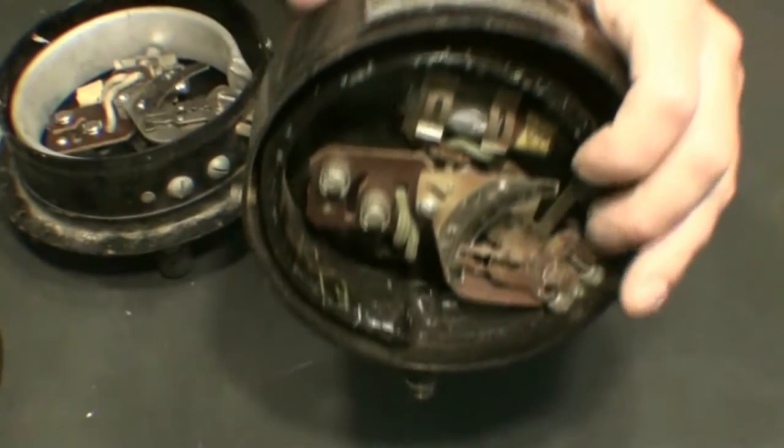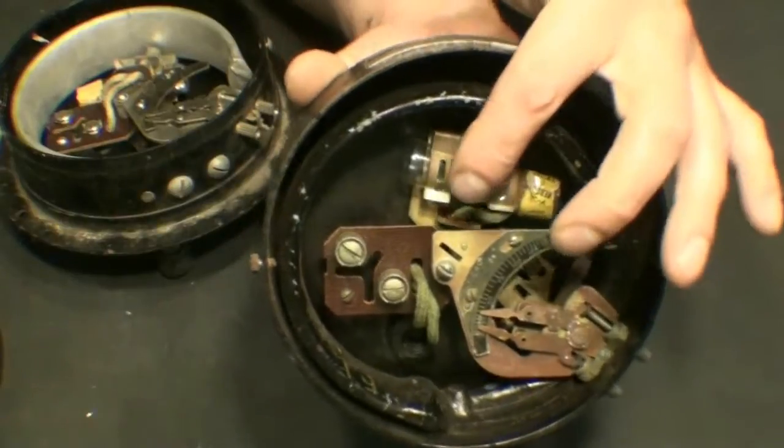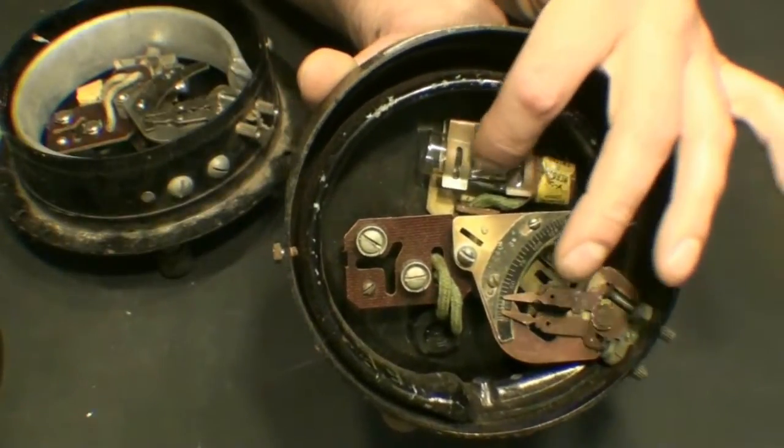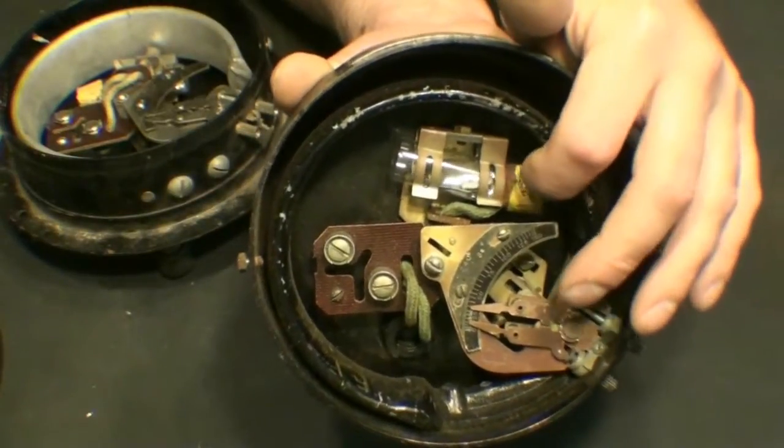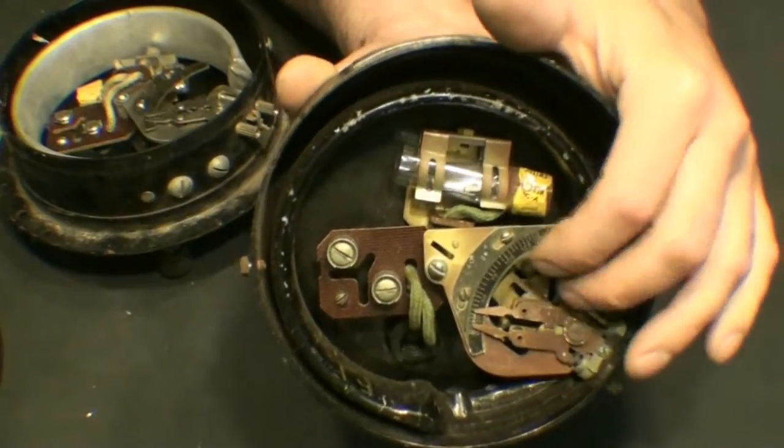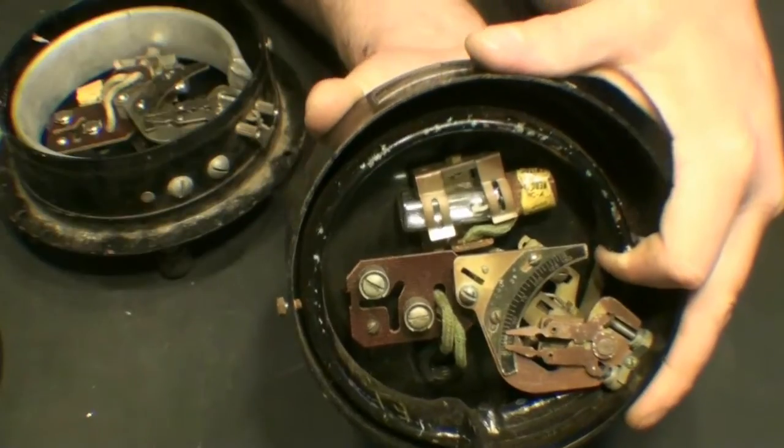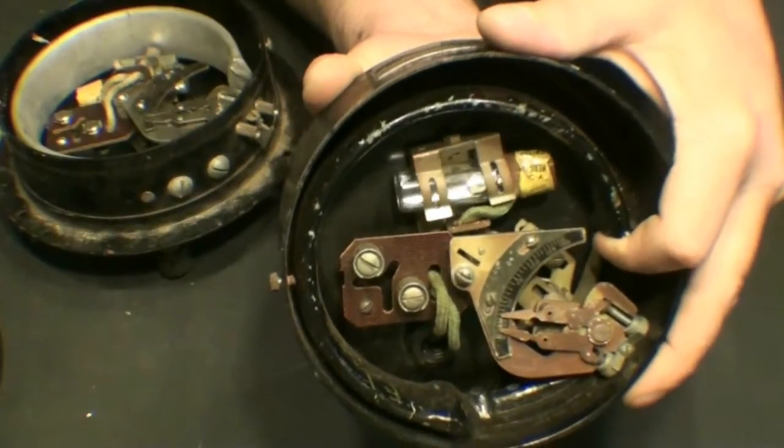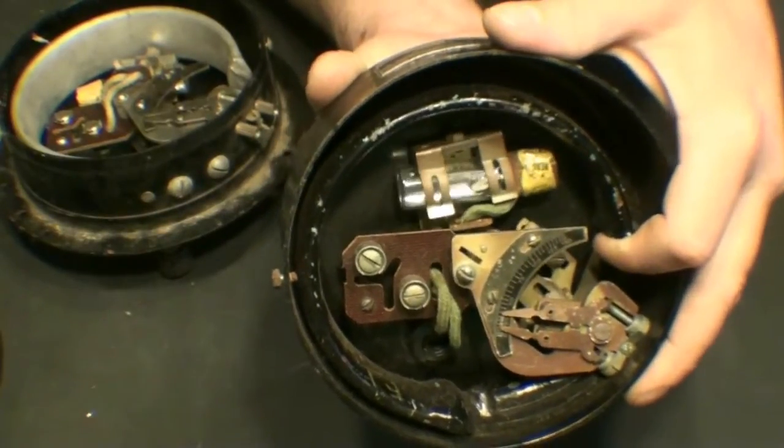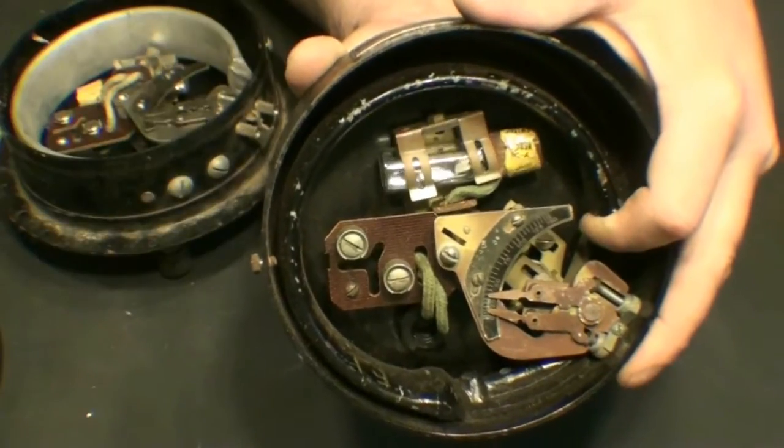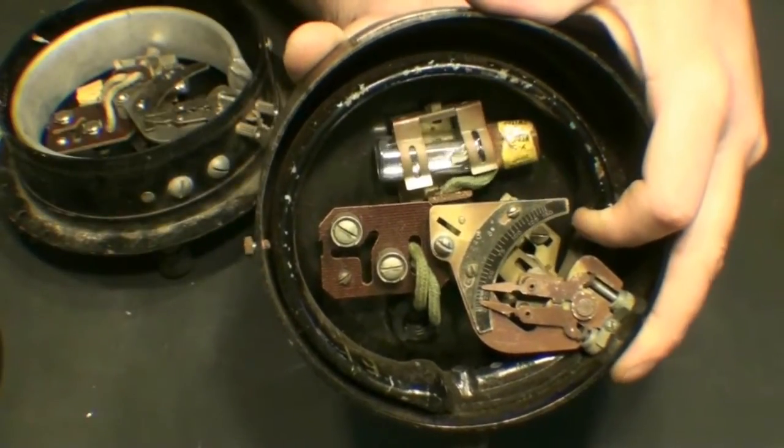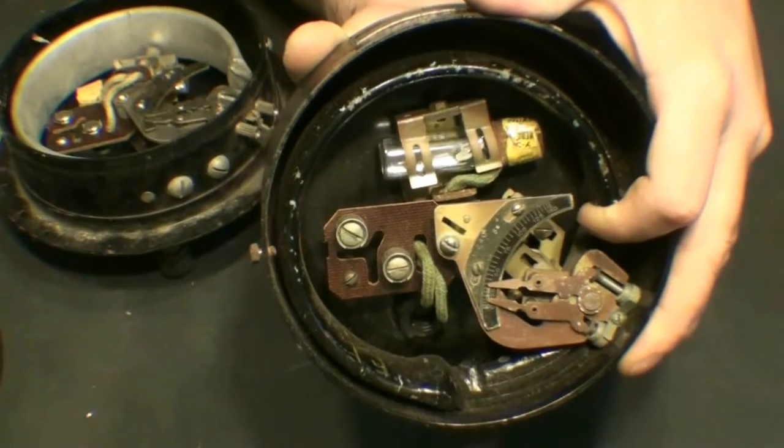How it operates is you have your little glass tube up here with the mercury inside, similar to an old-style thermostat. As the pressure rises, the mechanism tilts that vial of mercury and either makes or breaks the connection.